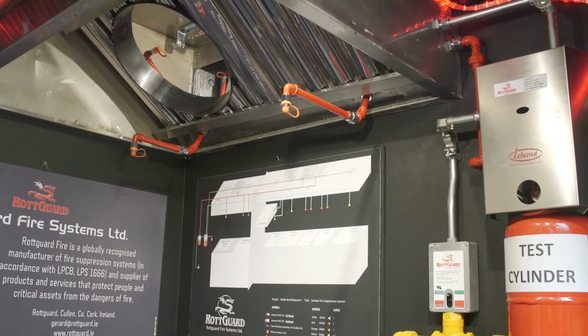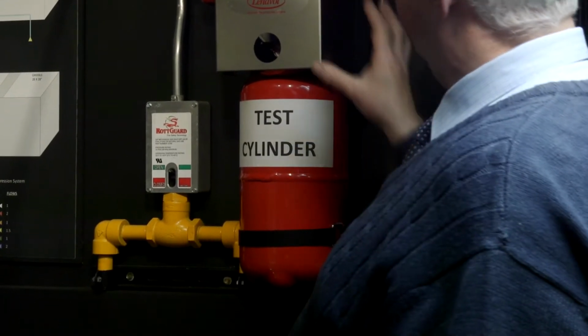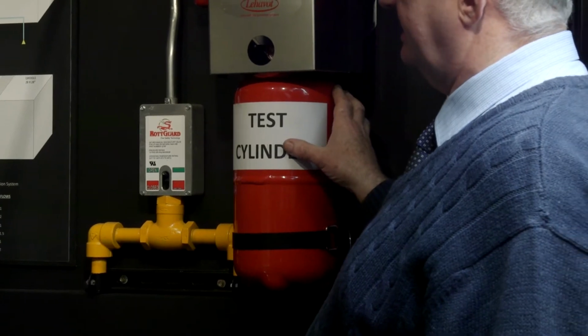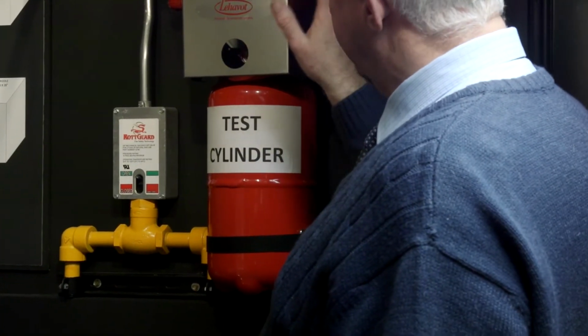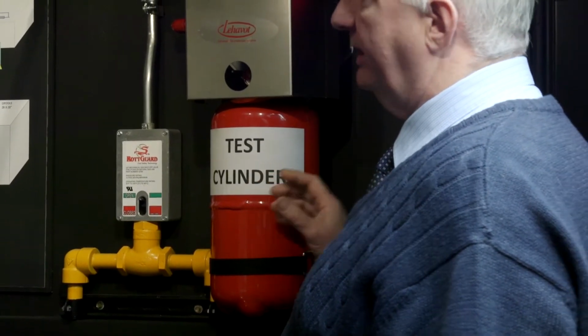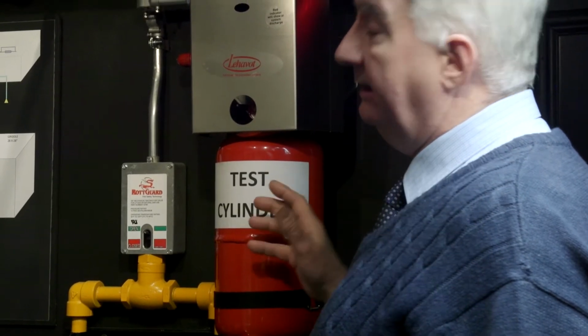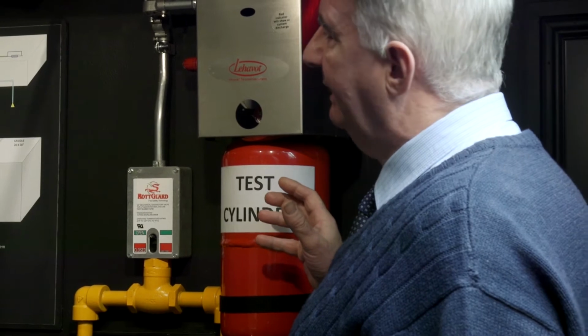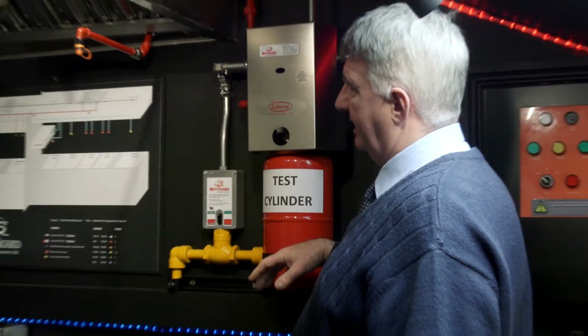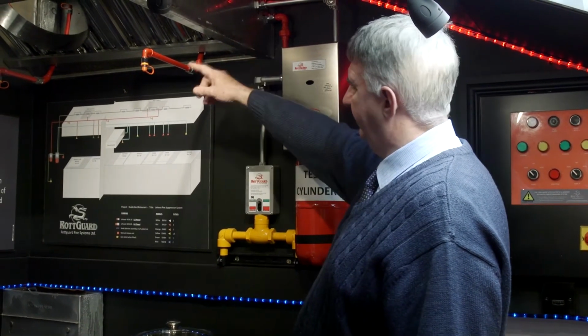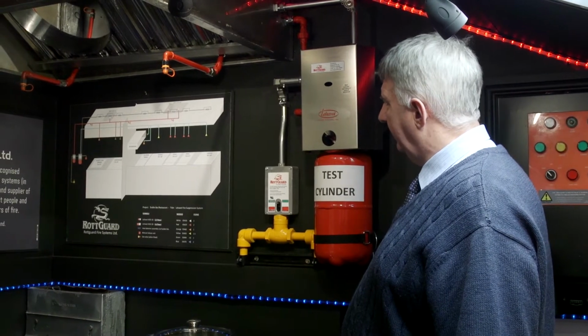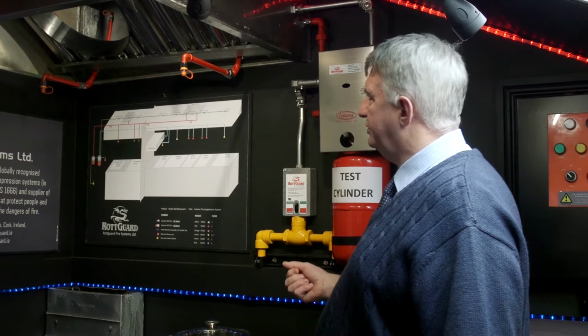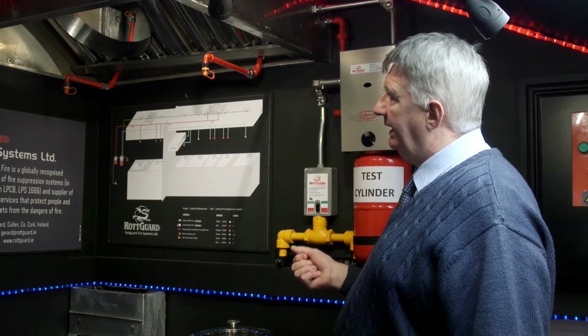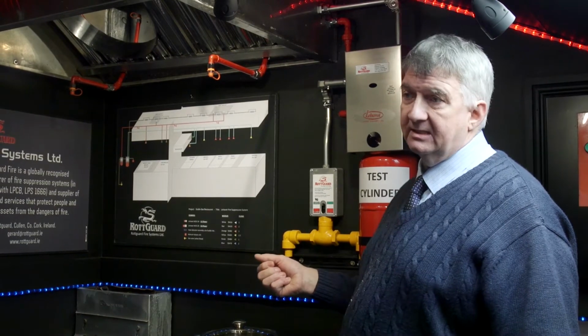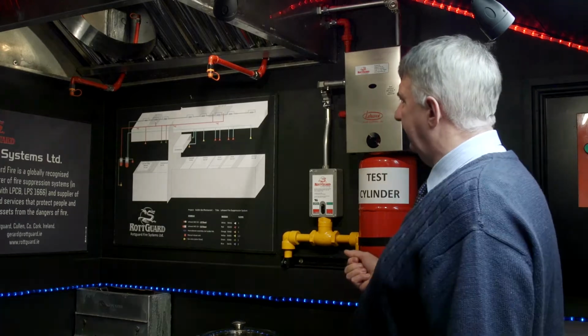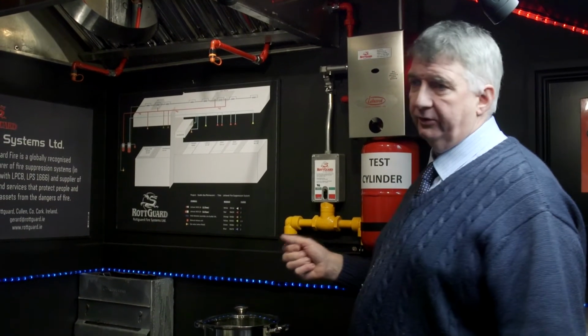And also they have a feature with them that this safety pin here, used to arm the system in the first instance, has to be removed before this cover can be put back on. So you couldn't have a situation where somebody servicing the system inadvertently fails to refit a gas cartridge used to discharge the agent out through the discharge pipe here and nozzles as is seen here. We have supplied several of these systems for use in hotels, fast food, in restaurants and canteens, in factories and schools, and we think it's a very good system compared to others.